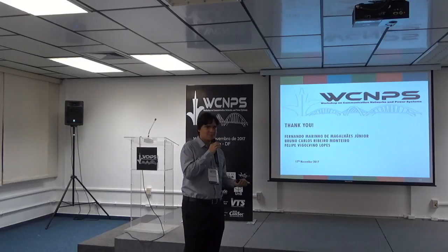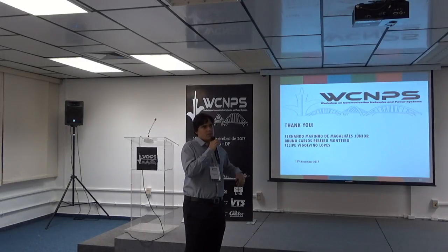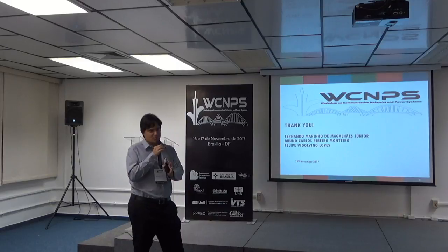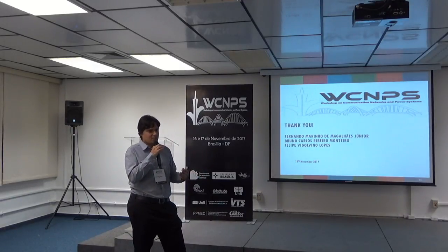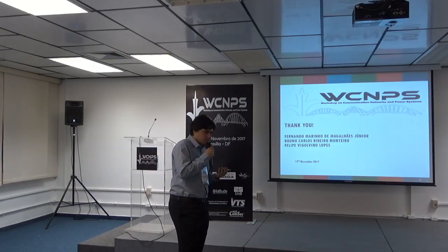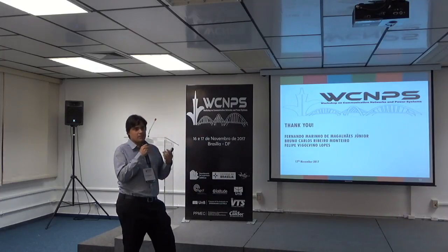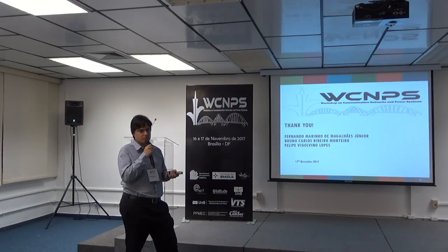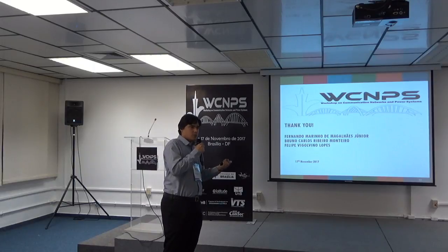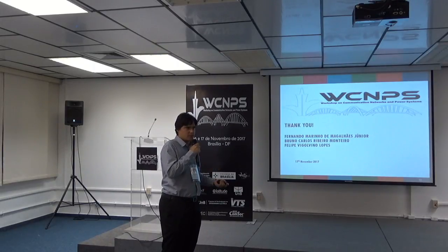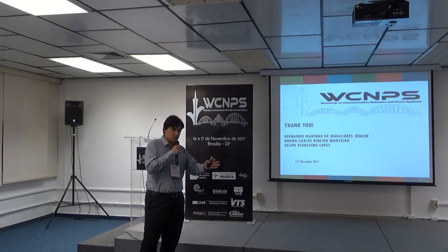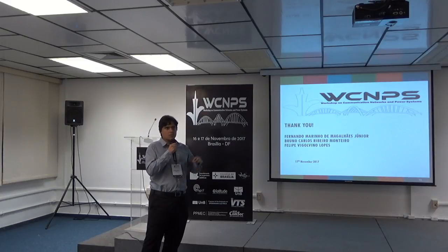But I have an argument. Traveling wave occurs quickly. It's only the time for the wave to travel from the fault to the terminals. There is not enough time to see saturation. For traveling waves, a point of a problem is the CCVT, because it does not have a good frequency response. Then we could not identify the voltage traveling wave correctly, or not identify it at all.